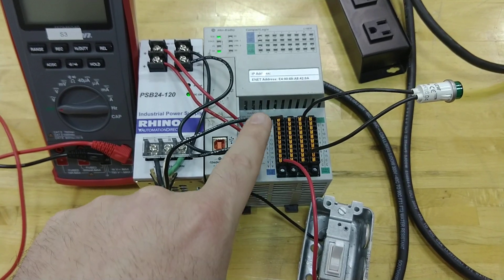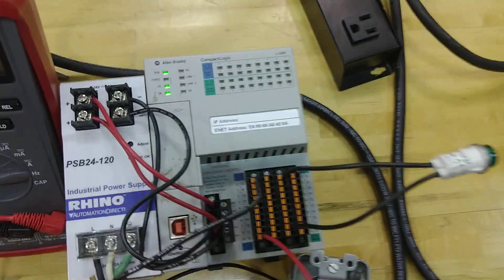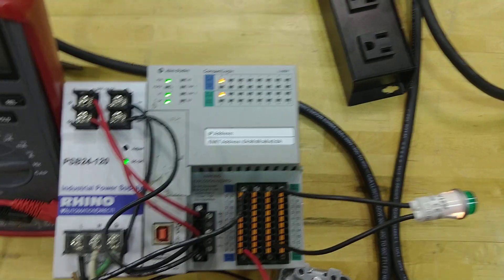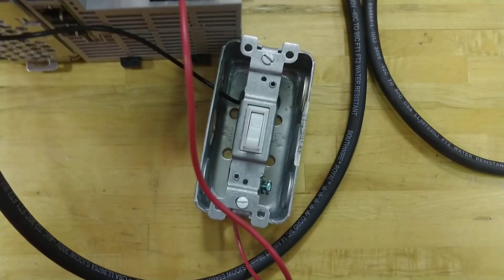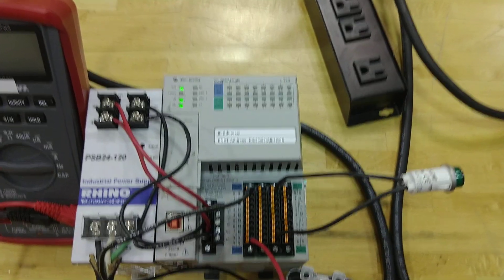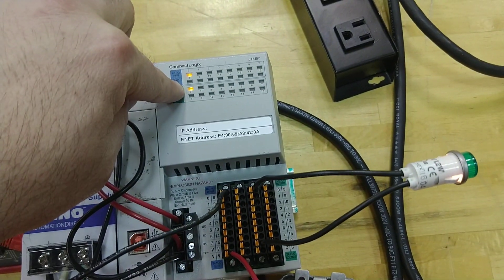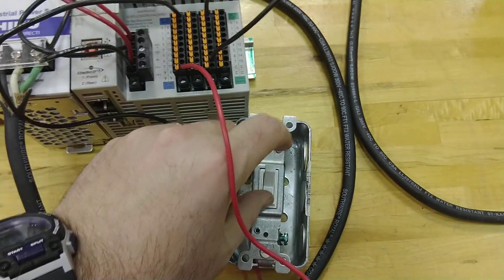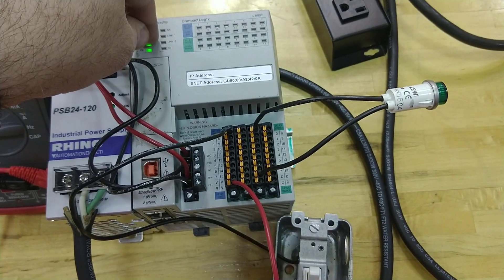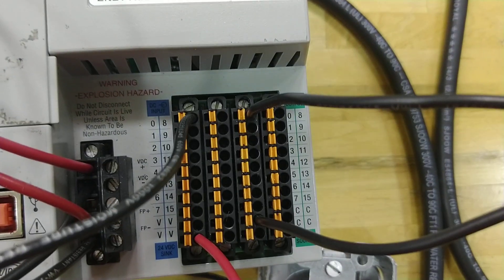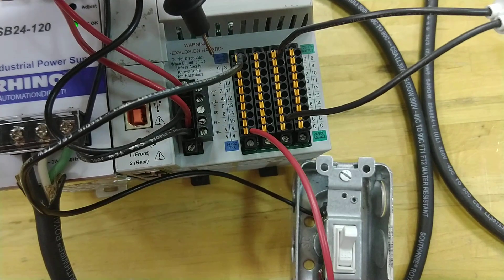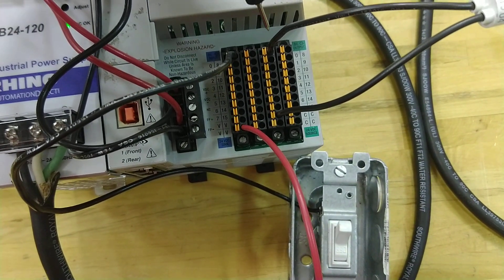And if I'm just going to wire this with a lot of outputs, a lot of inputs, I would run everything off the terminal blocks because I only have one input and one output. There's nothing there. And now take a look. When I flip the switch here, you can see a light turned on that corresponds to that being turned on. And if I flip the switch, then it turns off. Now you happen to see the output turning on because there's logic in there and you can see on this light that it is on. That corresponds to that right there. Because the input is switched, sends a signal to the input card, and the logic inside the processor is going to be telling then the output zero to turn on. And you can see how those are corresponding. So grab my probe again, you can see that the zero is corresponding to here and the zero is corresponding to there.